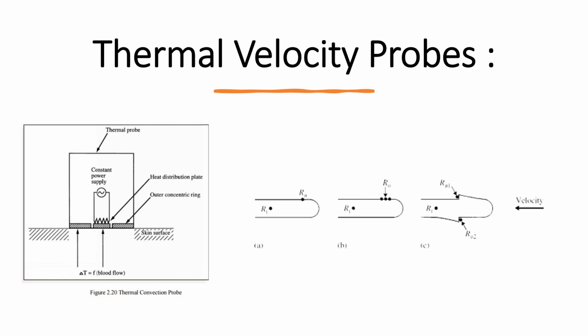Catheter probes are designed with two types of sensors. The first type uses the thermistor shown in figure A, which is cooled equally for both directions of velocity, and the output of the instrument is a full wave rectifier replica of the true velocity. To overcome this limitation, two additional thermistors are located downstream and upstream from RU as shown in figure B. Depending on the direction of velocity, one or the other is heated by the heat carried through the blood from the thermistor RU. These two additional thermistors are placed in a bridge that is balanced for zero velocity. A comparator detects the bridge unbalance and switches the output from positive to negative.